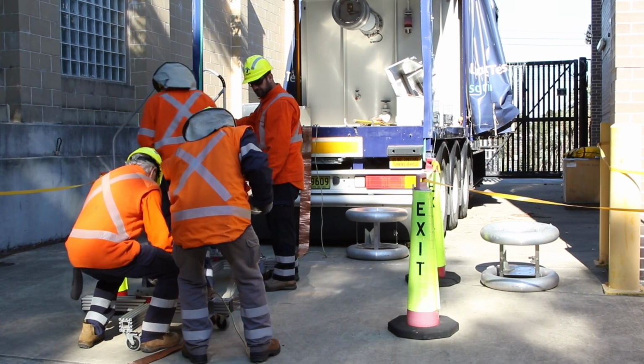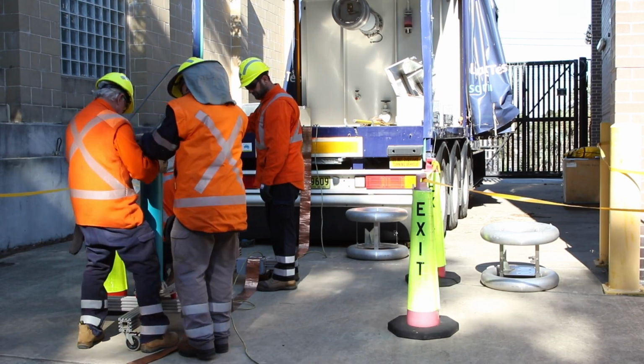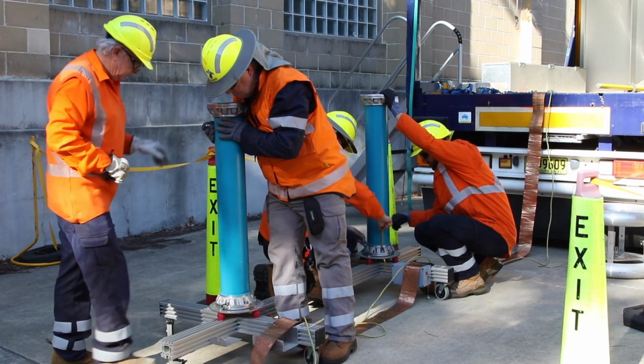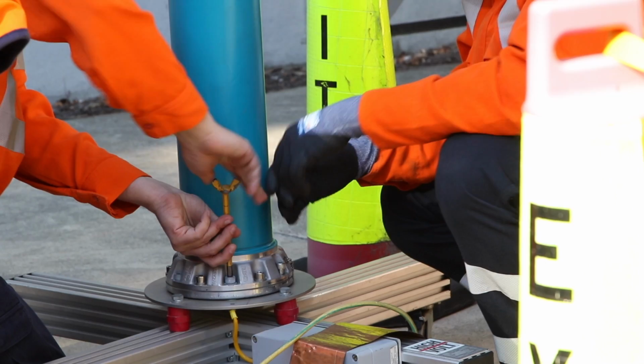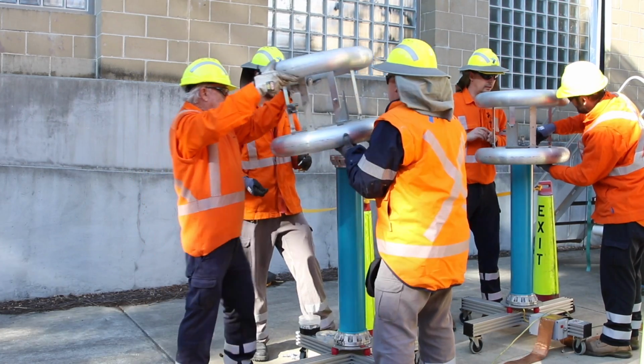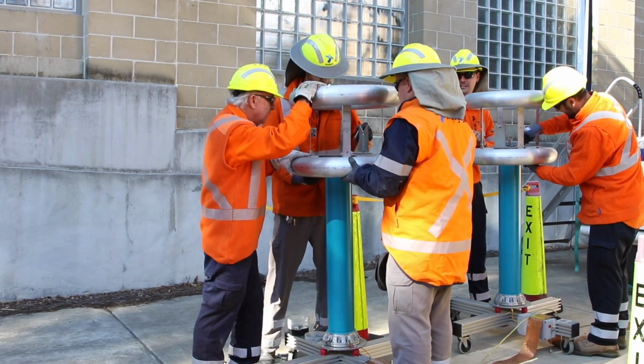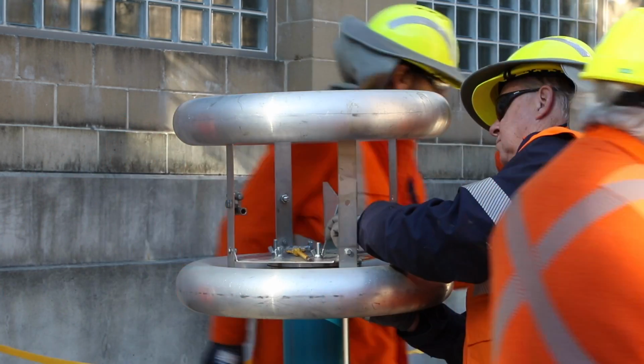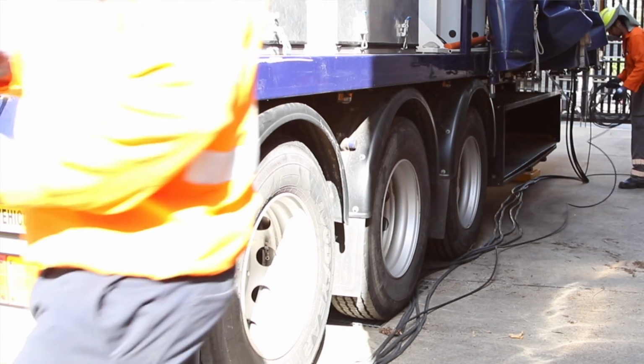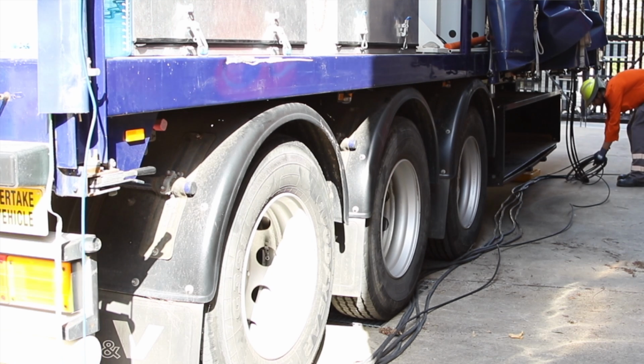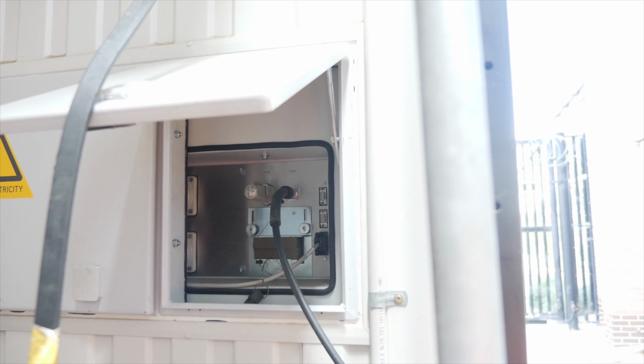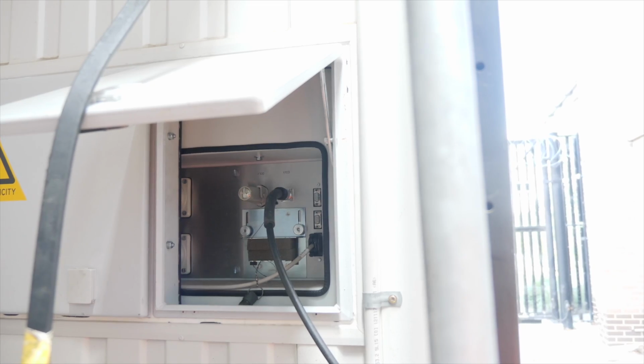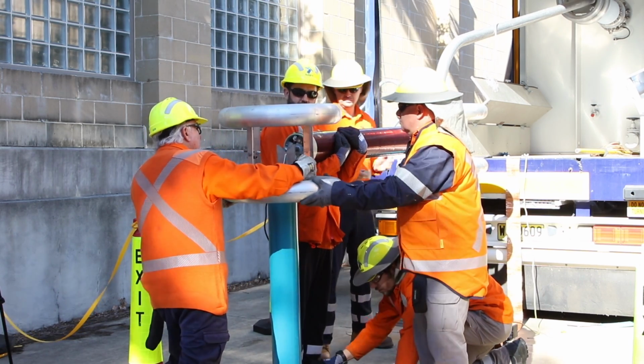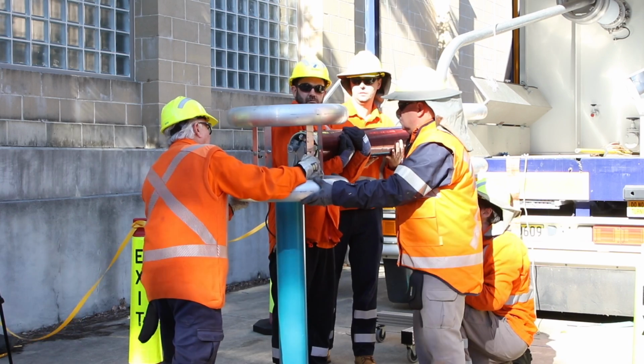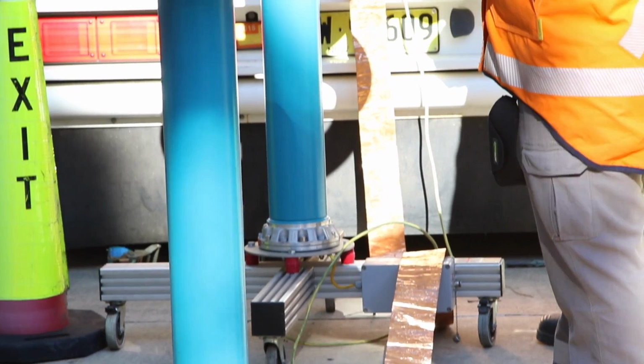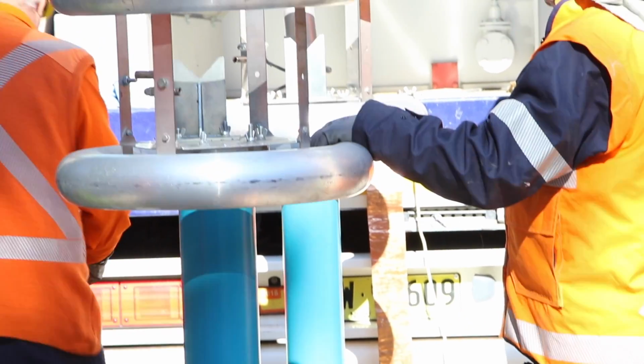The output voltage of the test trailer is monitored by a voltage divider. The arrangement of the capacitors and the inductor produce an output compatible with the voltmeter. The voltage divider is now measured and checked. Checking that these are set up correctly requires a ratiometer. The output is connected to the voltmeter via a low voltage cable to allow the safe verification of the output voltage of the trailer being applied to the test object. In this case, the test object is the 132 kV cable intended for commissioning. The wide copper earthing is used to connect a suitable earth to the measuring circuit.